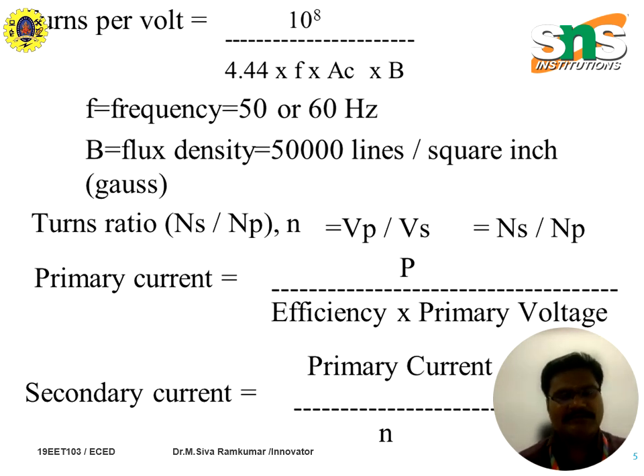For the secondary, we begin with this formula shown on the display, where F refers to the frequency, which may be in the range of 50 to 60 hertz, AC is the core area, and B is the magnetic flux density, around 50,000 lines per inch.